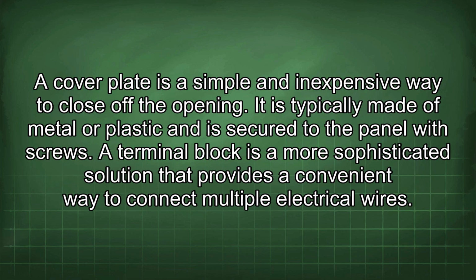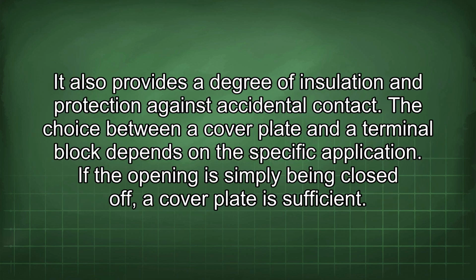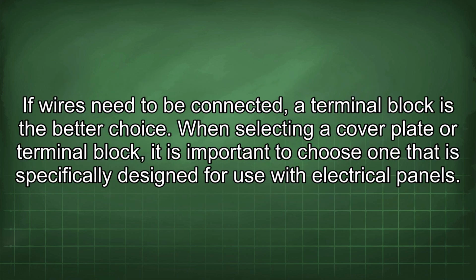A cover plate is a simple and inexpensive way to close off the opening. It is typically made of metal or plastic and is secured to the panel with screws. A terminal block is a more sophisticated solution that provides a convenient way to connect multiple electrical wires. It also provides a degree of insulation and protection against accidental contact. The choice between a cover plate and a terminal block depends on the specific application. If the opening is simply being closed off, a cover plate is sufficient. If wires need to be connected, a terminal block is the better choice.